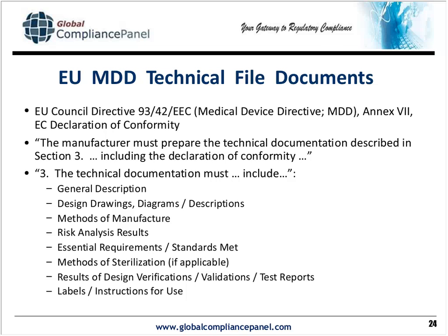And then they audit your technical file or design dossier, usually a desk audit, to make sure that not only do you have the quality management system functioning, but you meet the specific requirements of that type of product. And those two things then allow you to put a CE mark on your product and sell it outside the United States. Or inside too, for that matter, but the FDA could care less about a CE mark.